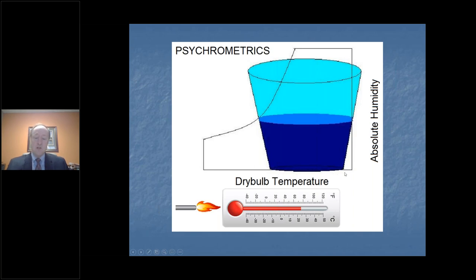So on the chart, I would go from left to right as I'm increasing temperature. As I'm adding moisture, I go from the very bottom, which is zero moisture, or zero grains of moisture, zero dew point. And as I add moisture into my pail, I add moisture into my airstream, and I would increase on the chart going from the bottom up to the top. So those are the two critical things to understand about the chart.